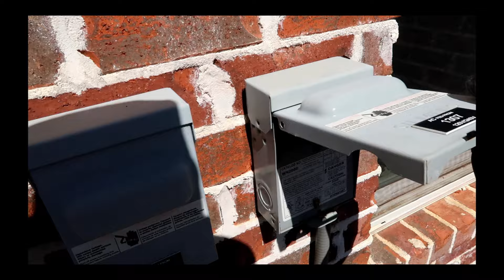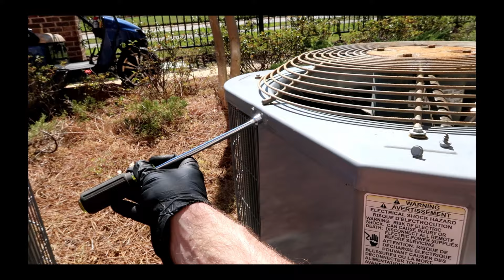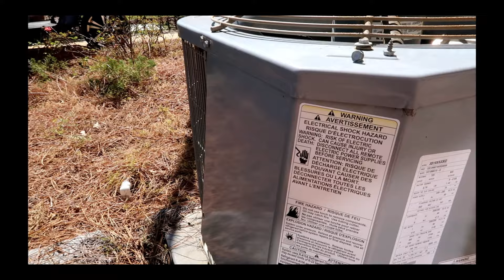Oh, here we are again, back at the condenser. Yeah, the air was blowing inside into the condenser, but it's supposed to be blowing out the top. I noticed when I did the contactor, I was looking at the capacitor, and it was new, so someone has been here before. You hook these up different from the Goodmans we have on the older side of this property. I think the yellow is the common and the blue is the Herm on these, where on the Goodmans, the yellow is the Herm. So maybe someone hooked it up wrong.